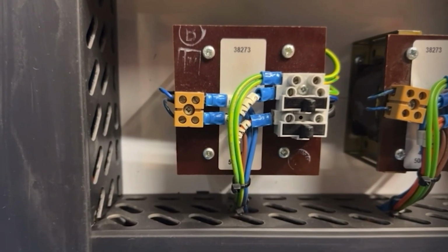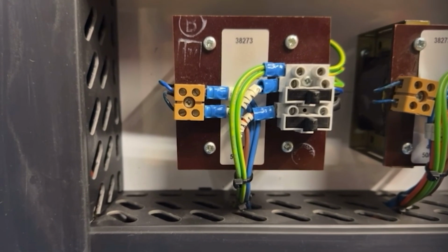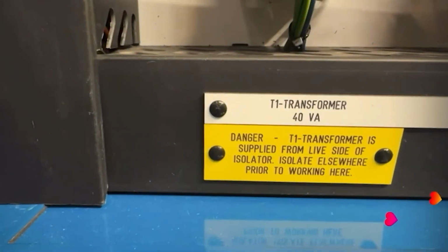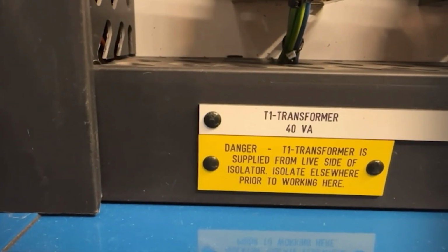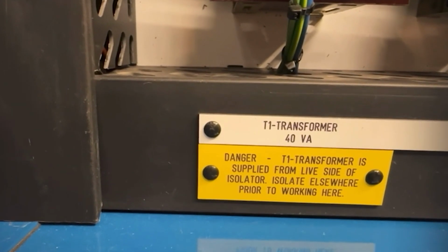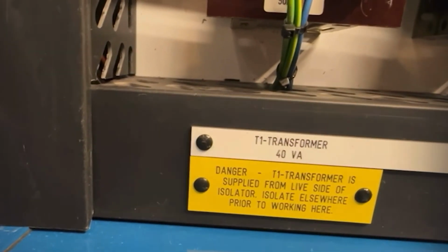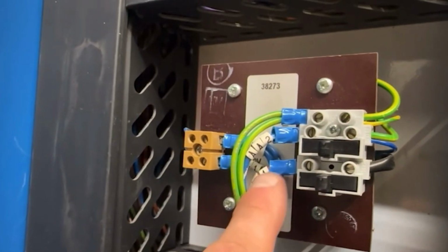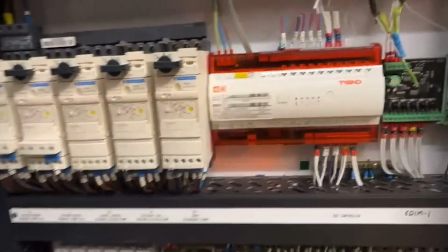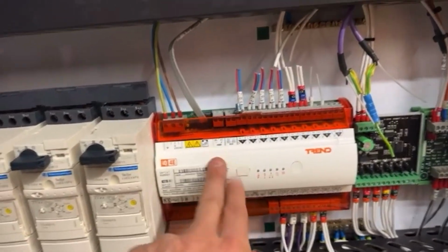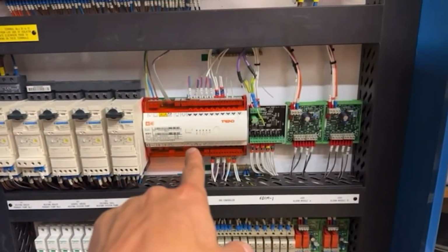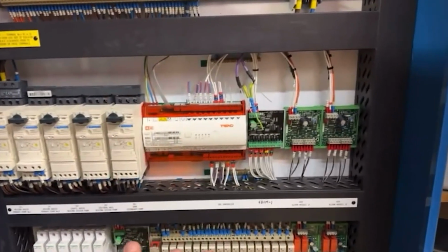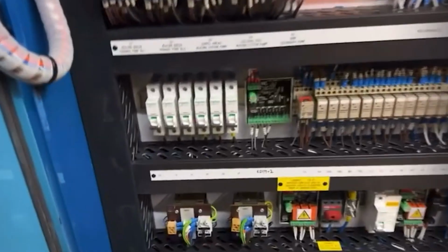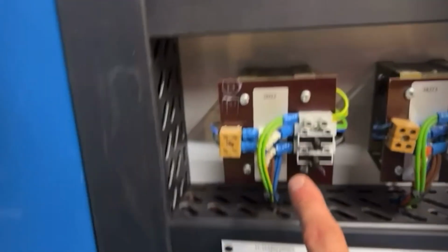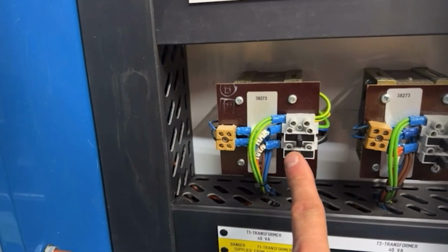So there we've got a 40 VA, 230 volt in, 24 volts AC out transformer. And it says, danger, T1 transformer is supplied from the live side of the isolator. So basically, when you turn this panel off, T1 stays live, which you're probably thinking is a bit weird. But look, it's got the numbers on it, AA1 and AA2. I heavily suspect, and I'm starting to guess now because I can't help myself, that goes to the controller. So if you turn the panel off in the plant room, wherever it's being remotely monitored from, it will communicate that it's off. And that is the purpose of it not isolating. We'll find out what that does later, but I think that keeps the essential control circuits live.